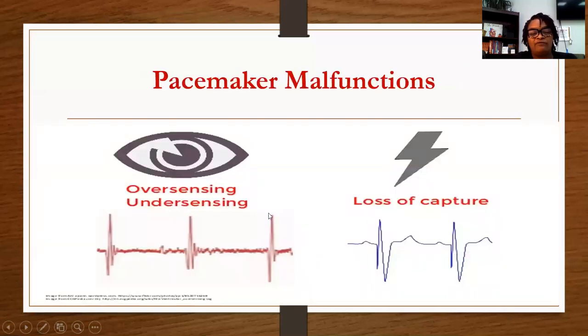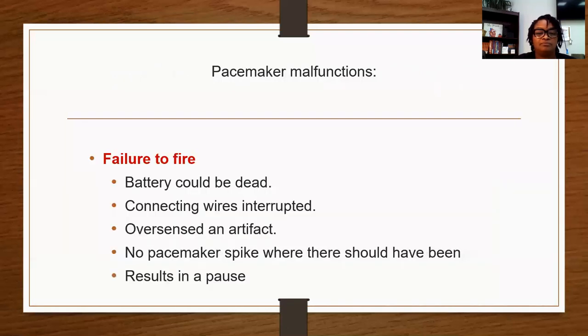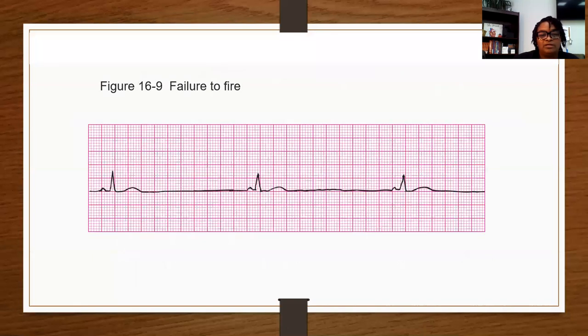Okay, so pacemakers can malfunction, you guys. They can oversense, undersense, or fail to capture or sense at all. And if that pacemaker fails to fire, some possible troubleshooting things can be the battery could be dead, the connecting wires could be interrupted, it could be oversensed, an artifact, no pacemaker spike where there should have been a pacemaker spike, or results in a pause. Here's an example of failure to fire. You see there's not any pacemaker spikes where they should be.